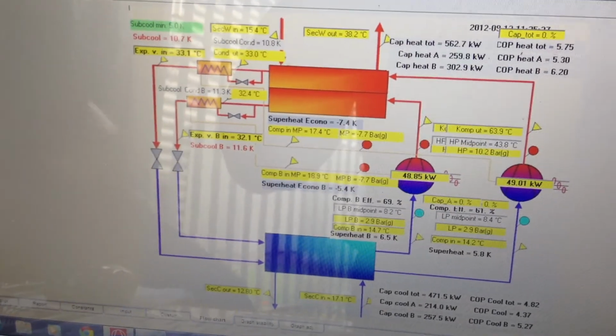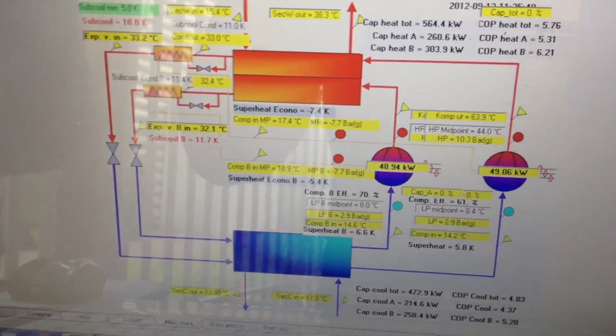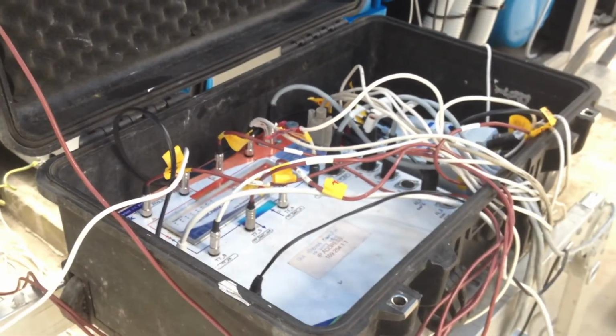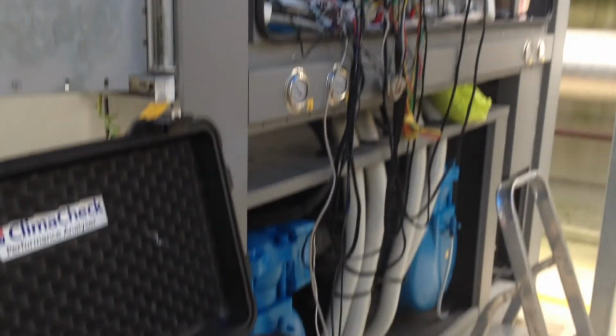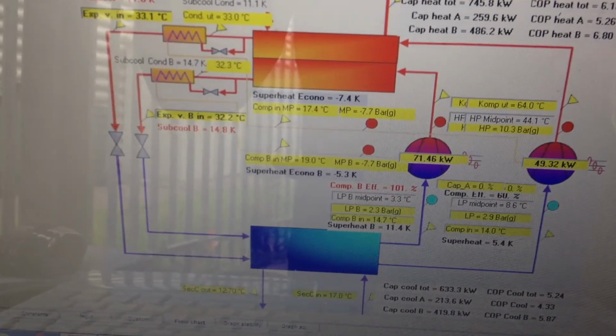In this example we're looking at a twin circuit water chiller with economizers on both circuits. Here is the water chiller being monitored with ClimaCheck. Twin screw compressor machine. And here we can see the power input dynamic with one machine partly unloaded. And you can see every parameter, including the subcooling economizers and their behavior, the superheat settings, stability of the system, cooling capacity for each circuit and the total, the heat rejection for each circuit and the total, isentropic efficiency of the compressors, power input, system COP in heating and also in cooling.